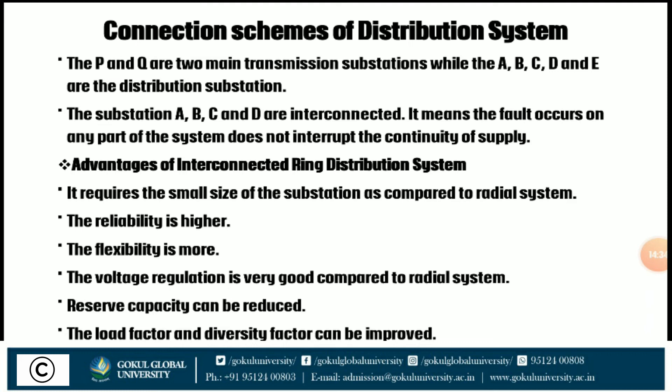In the interconnected grid system, points P and Q are the main transmission substations, while A, B, C, D, and E are distribution points. If a fault occurs on any part of the system, it does not interrupt the continuity of supply. Advantages: it requires smaller size substations compared to radial systems; reliability is higher; flexibility is more; voltage regulation is very good; reserve capacity can be reduced; and load factor and diversity factor can be improved.